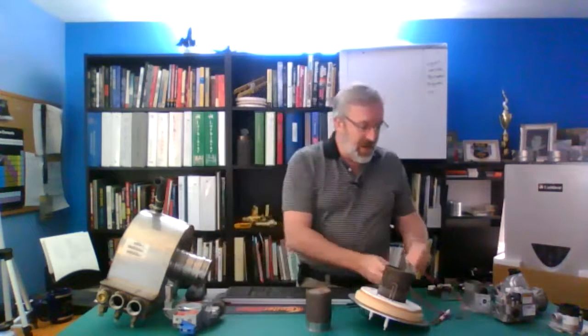What that resistor is within the boiler, the control panel, there's some communication between the fan and the control where we're kind of using this pulse width modulation signal. And we send the signal out and the signal's got to come back. So it's kind of a boiler telling the fan, I want you to do this, the fan coming back and saying, here's what I'm doing. And that signal can get interfered with, and that's why there's a resistor in there to kind of prevent that from happening. So just check and make sure you have that.